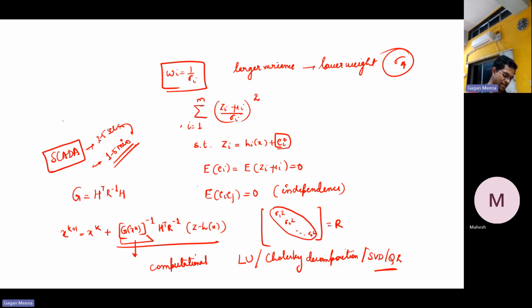Now we have PMUs only at substations of 400 kV and above. Below that we don't have PMUs. Below that we still have SCADA. Now we have to integrate these two, measurements from SCADA as well as PMU. So it becomes a hybrid state estimator. We have measurements from two different sources, one from SCADA and one from PMU. PMU is giving data at a very fast rate, and SCADA is giving data at a much slower rate. So there is a difference in time scale. And we still want to use these two together to get a better state of the system.